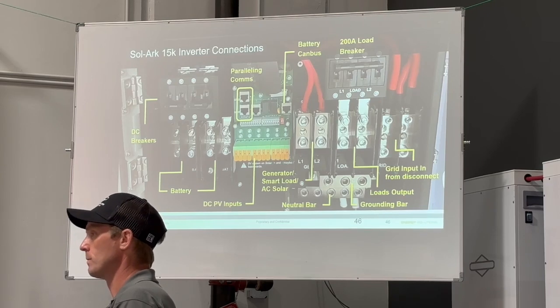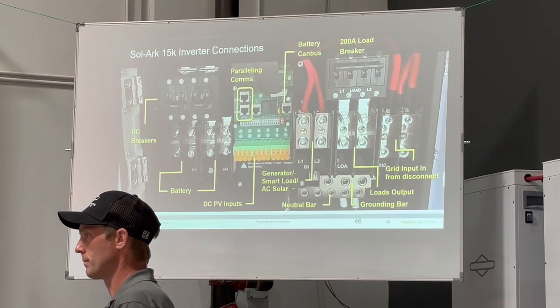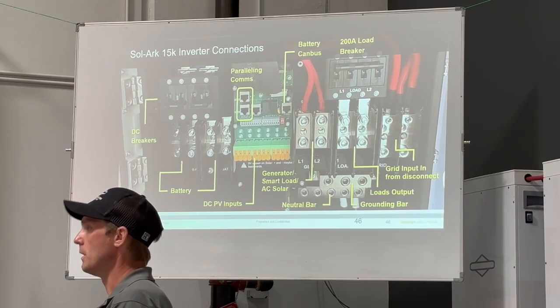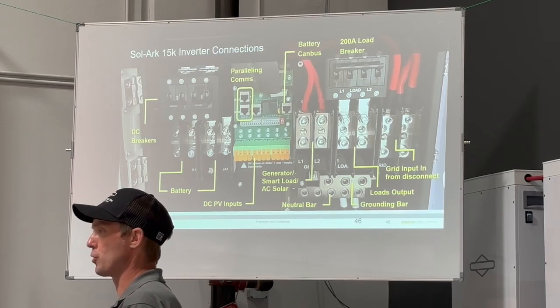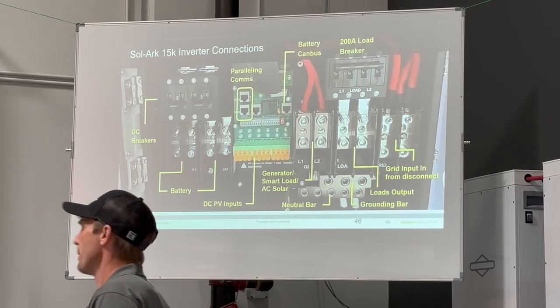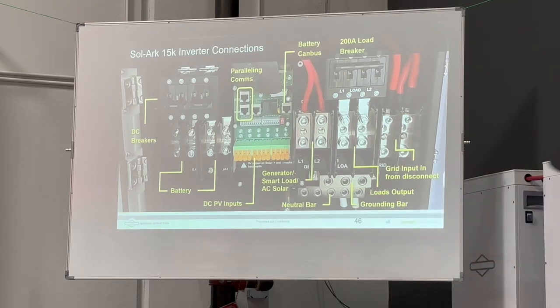So if you're using one of the blocks, you come in from your battery stacks into the block, and then you're running 2 cables out of the blocks to both inverters. If you had 3 inverters, the same. Yep. Really helpful.